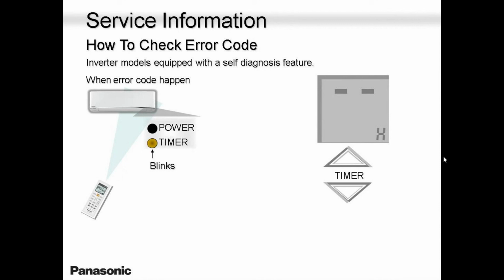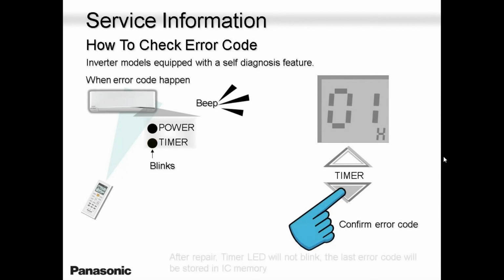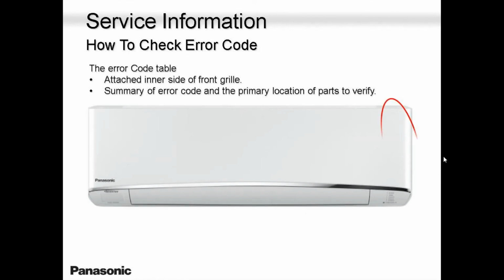How will you pull the error code? Very simple. Take the remote controller, use a toothpick or a pin, a thick pin that goes into the check slot. It goes into the check hole, press and hold for 5 seconds. What you're going to see on the right side here is 2 dashes, okay? Not with the temperature button up and down, but with the timer button up and down. Scroll. You will scroll until you hear the indoor unit beep. It will beep 3 beeps, like tit tit tit or tit tit tit tit. When you hear that beep, hold on, stop, and look at your remote controller screen, and it will tell you what error code you have.